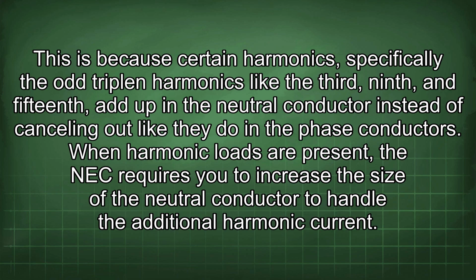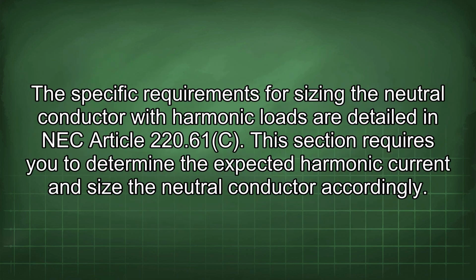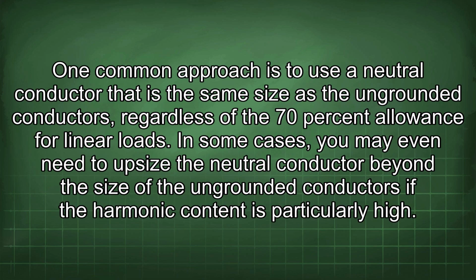When harmonic loads are present, the NEC requires you to increase the size of the neutral conductor to handle the additional harmonic current. The specific requirements for sizing the neutral conductor with harmonic loads are detailed in NEC Article 220.61(C). This section requires you to determine the expected harmonic current and size the neutral conductor accordingly. One common approach is to use a neutral conductor that is the same size as the ungrounded conductors, regardless of the 70% allowance for linear loads.